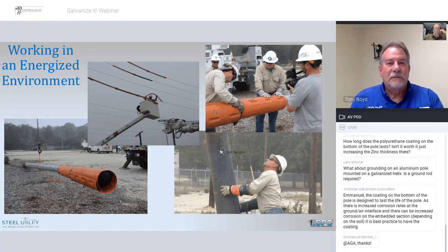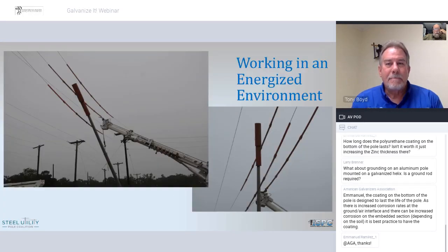And you can see, remember, our poles are conductive, as Tony showed by the testing that he did on the pole that was in the very first slide. So here he's wearing a pair of 20 kV gloves, setting a pole in a 15 kV circuit. And if that pole comes in contact with the circuit, that pole is going to become energized, and these gloves will protect them. Now, you're going to see later on in this slide, we're setting in the conductor. So if we're setting in the conductor and the steel pole comes in contact and the pole becomes energized, and we have to assume that it can be, because you can bang hard enough against these connectors on the hose that they will come apart.